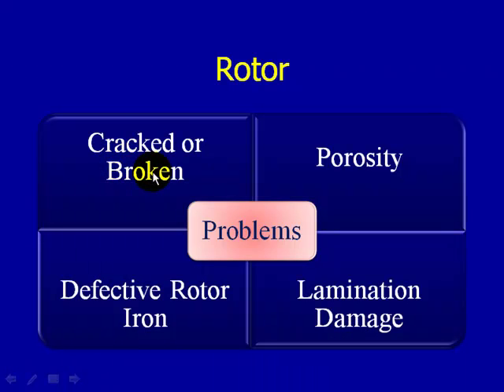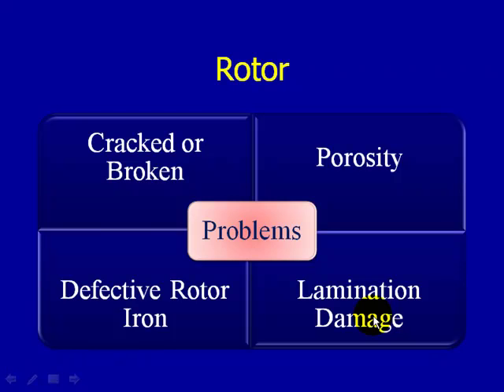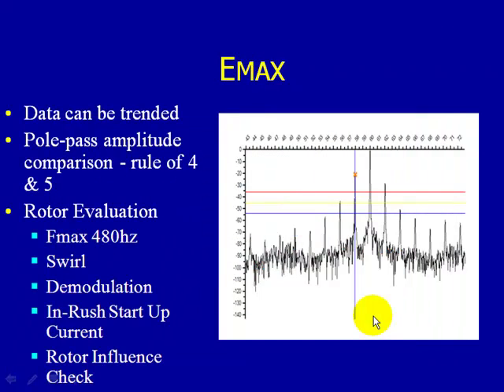Some of the problems that can occur inside the rotor include cracked or broken rotor bars, porosity in the cast aluminum design, defective rotor iron, or lamination damage. These broken bars, porosity, or other problems create heat or high temperatures and a subsequent loss of torque. So it's important that we monitor the rotor, make sure it's healthy, and that it's operating in a good, stable condition.